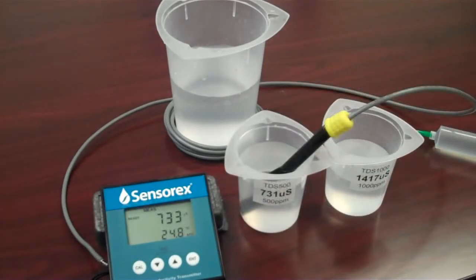Okay. Most users will be using automatic temperature compensation during conductivity measurement. Verify the temperature reading of your sample by using a thermometer in the test beaker. I've already tested the temperature of these beakers and my accuracy of temperature is well within 1 degree Celsius. If you're more than about 2 degrees Celsius off, you'll want to perform temperature recalibration as described in your user's manual. If you do not use automatic temperature compensation, you should select the manual temperature compensation mode from the setup menu in your instrument and put in the actual temperature you are using in the calibration standard.